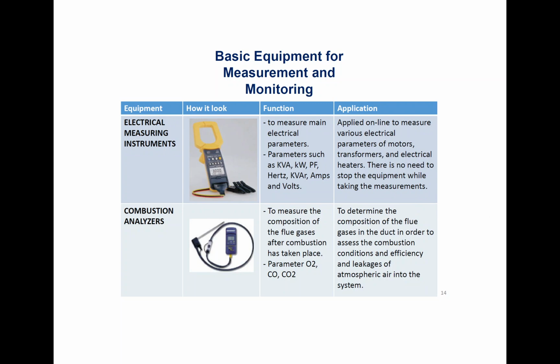It doesn't matter what brand, the important thing is the function is to measure main electrical parameters: kVA, kilowatt, power factor, frequency, kilovar, reactive power, current and voltage. Our goal is to know the real loading of our motors, transformers, electrical heaters, not based on the manual but based on the online installed system, including all the wiring and related equipment, whether installed radially or in parallel, so on and so forth. We need to know this.